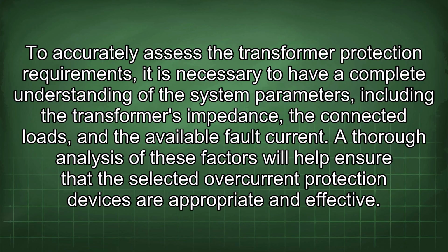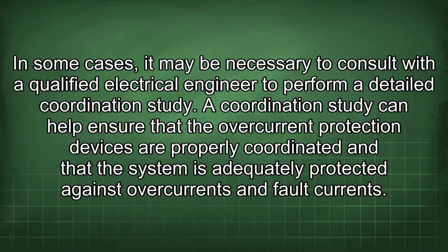A thorough analysis of these factors will help ensure that the selected overcurrent protection devices are appropriate and effective. In some cases, it may be necessary to consult with a qualified electrical engineer to perform a detailed coordination study. A coordination study can help ensure that the overcurrent protection devices are properly coordinated and that the system is adequately protected against overcurrents and fault currents.